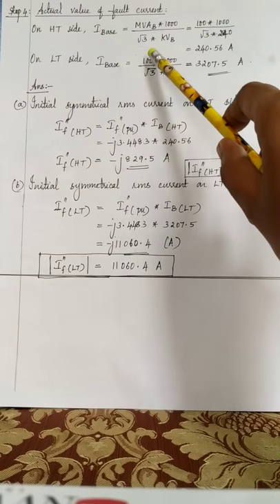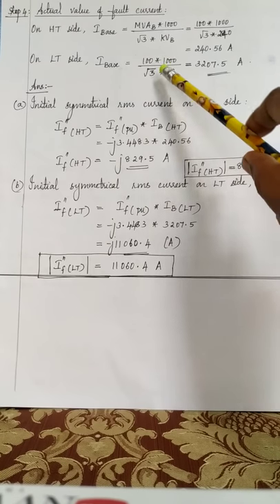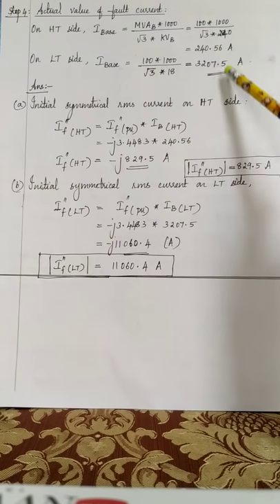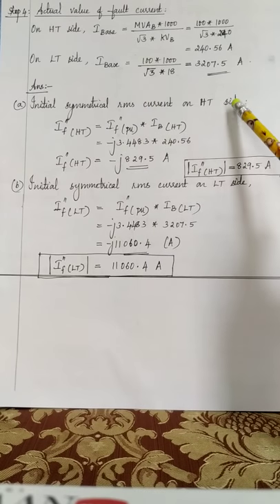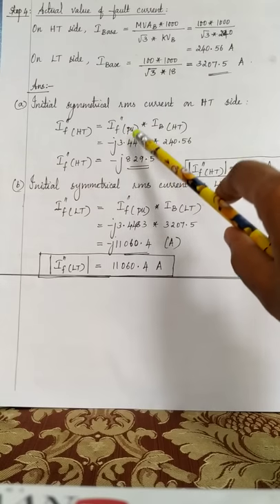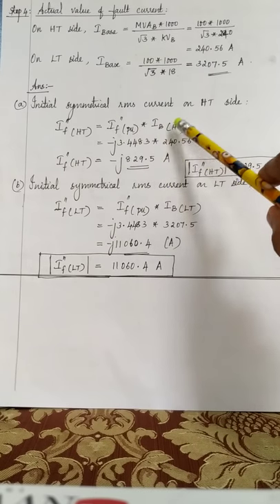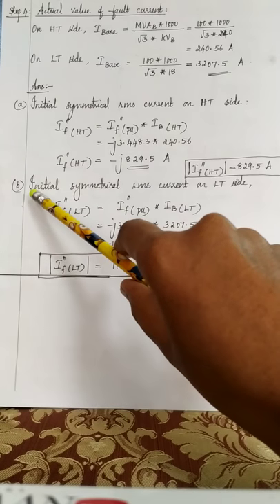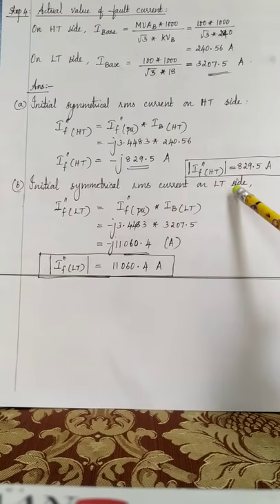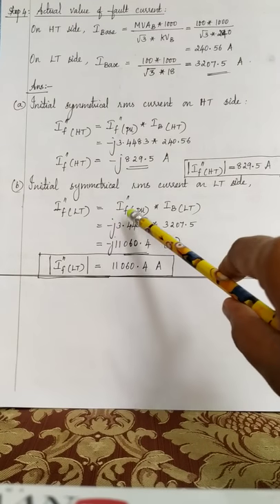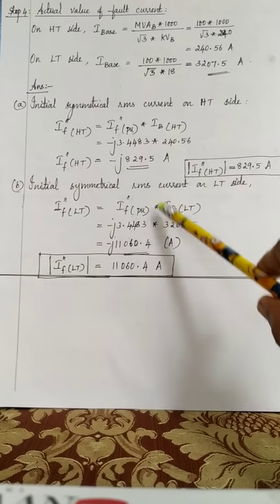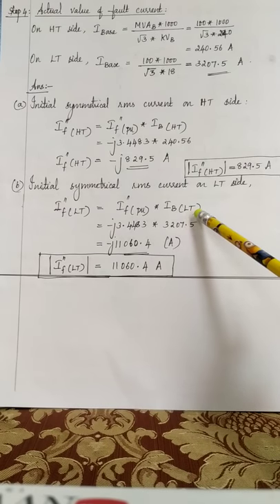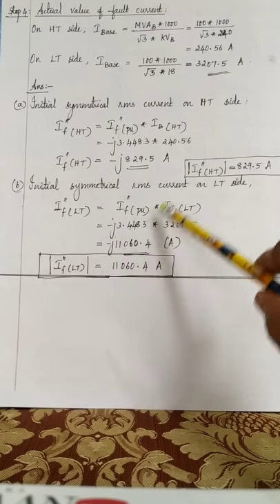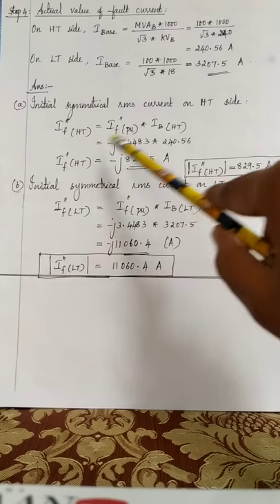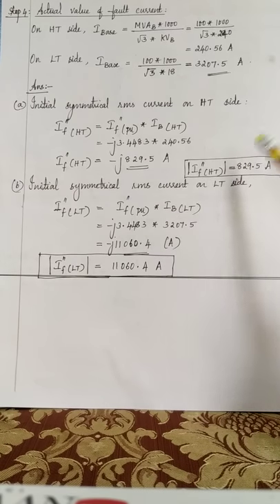On the LT side, 100 MVAB, 18 KVB, section 1. The LT side falls on section 1. You got the base current. So now the solution, A part. The initial symmetrical RMS current on the HT side is IF double dash HT equal to IF double dash per unit into IB HT. Similarly, B part, the initial symmetrical RMS current on the LT side: IF double dash LT is equal to IF double dash per unit into IB LT. Okay, so you got the value. This modulus, I have written only the magnitude by removing the j.